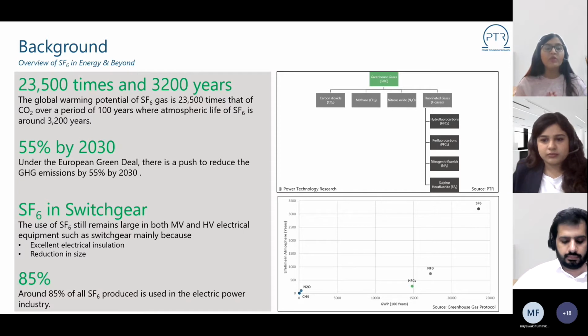Despite being such a harmful gas, it is extensively used in the electrical industry, particularly in HV and MV switchgear. The main reason for employing SF6 in switchgear is its excellent insulation properties, arc quenching mechanism, and importantly, the reduction in size of the electrical equipment.